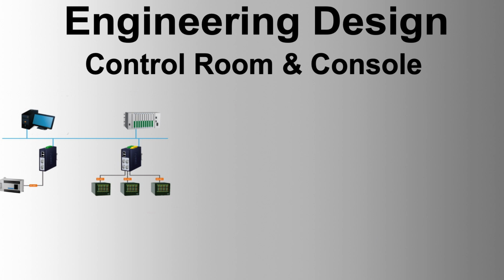Console configuration. Future expansion should be considered when determining the console configuration. The configuration of plant layout consoles in the control room should conform to the course of the process, from left to right, especially for alarm displays. Consoles should be grouped functionally for each part of the process. Mirror image layouts should never be used for identical processes. Console arrangements for different processes or parts of processes should be clearly separated.